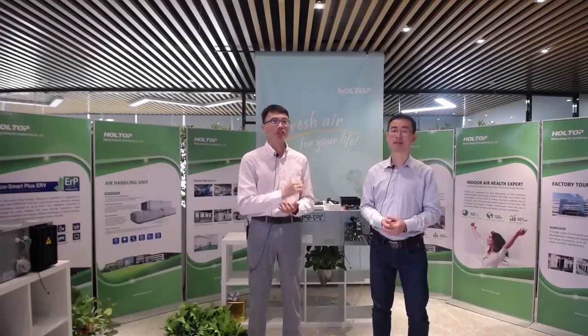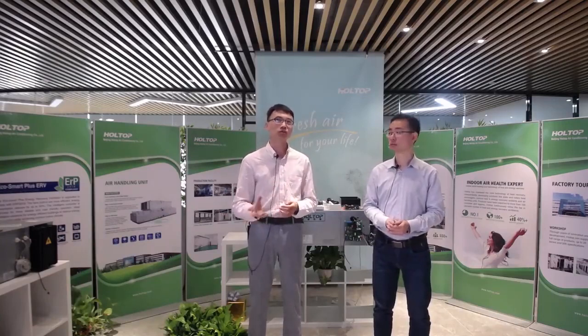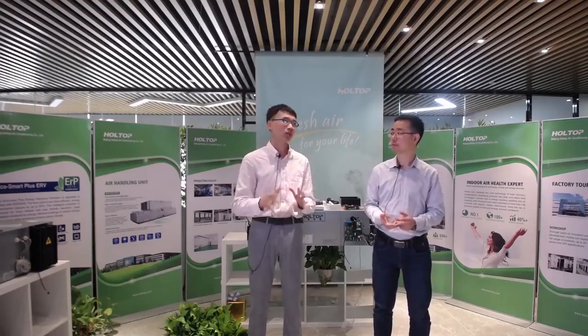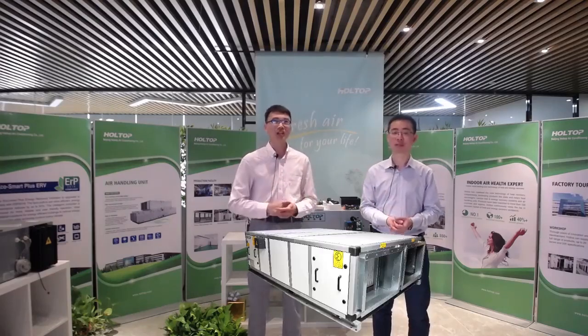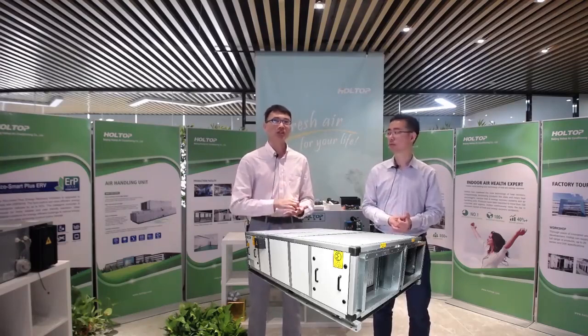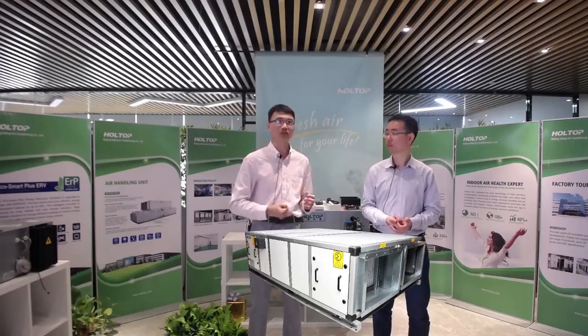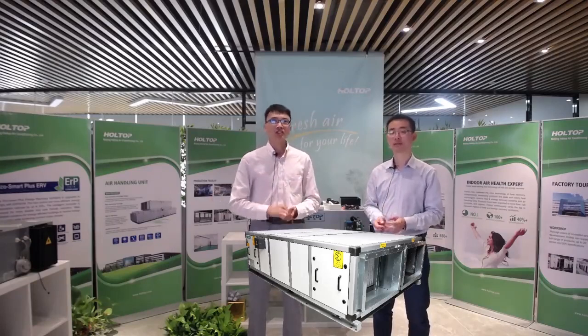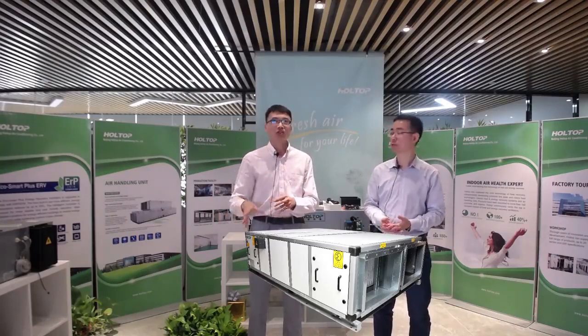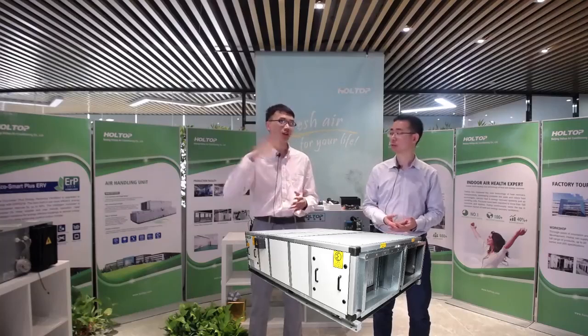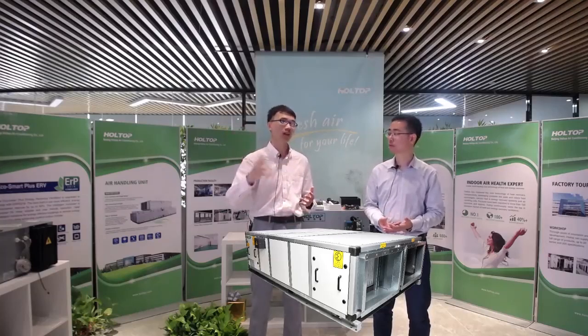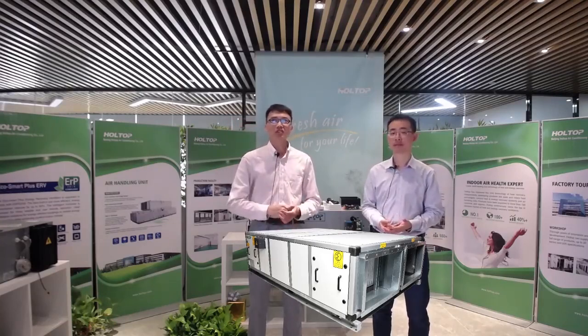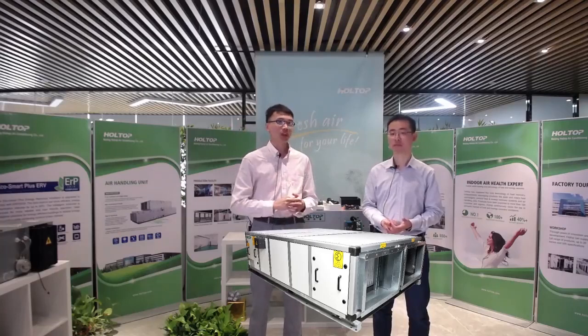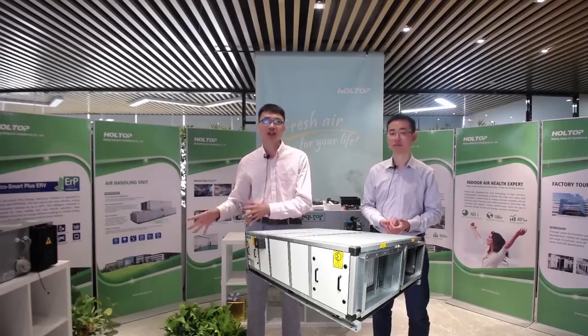So I'm going to introduce the functional sections of our indoor direct expansion units. Normally the indoor sections include the air inlet damper, and this damper can be manual type or motor type. The electric damper is driven by an actuator from the control system. After the air damper comes the filter. Normally we use G4 panel filters for offices, or we can use a higher class. Then there is the direct expansion coil, the supply fan, and the outlet flange connection.